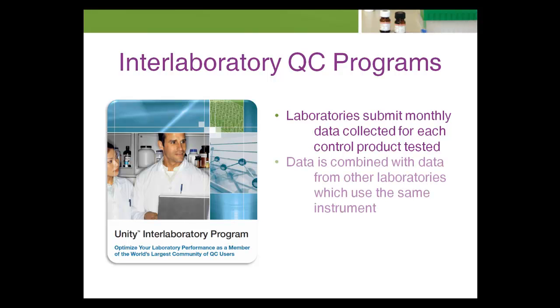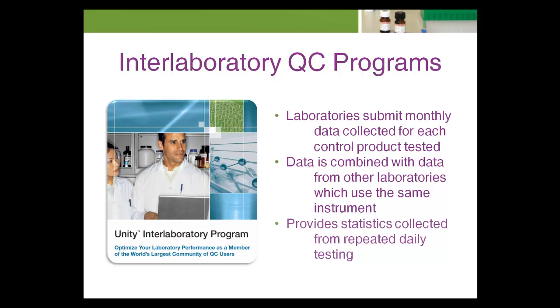In an interlaboratory comparison program, laboratories submit monthly data collected for each control product tested. These data are combined with data from other laboratories which use the same instrument. The benefit of an interlaboratory program over a proficiency program is that it provides statistics collected from repeated daily testing, whereas the proficiency program provides statistics collected from single events that occur only three times a year in the United States, and somewhat more frequently in other countries.